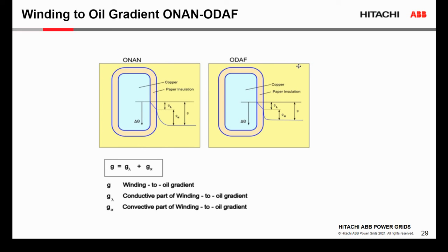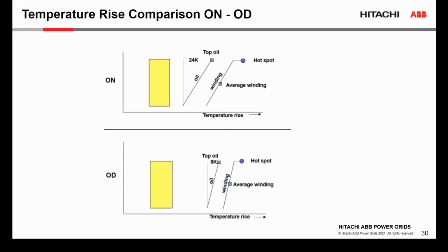But with the change to the ODAF type of cooling, we significantly reduce the convective part of the gradient. So the overall gradient between the windings and oil is much lower. And you can see how the gradient changes and how the top oil changes in transformers with natural oil circulation. Usually the top oil temperature rise on the top of the tank is much higher than the oil temperature rise on the bottom of the tank.